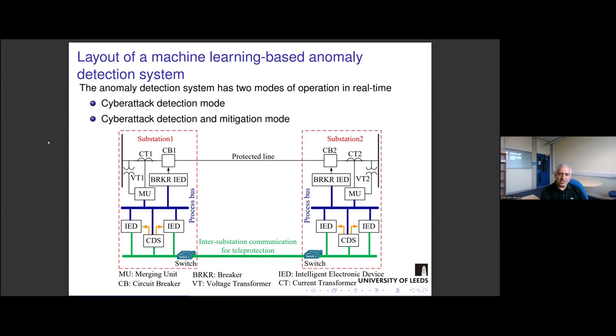We consider two modes of operation. This CDS, or cyber attack detection system, at the bottom of the figure is the one that we have developed. It has two modes of operation: cyber attack detection mode and cyber attack detection and mitigation mode. In the cyber attack detection mode, if it identifies an anomaly, it only generates an alarm to inform the operators of the substation that there is an anomaly in the measurements. And in the cyber attack detection and mitigation mode, after detecting the anomaly in the measurements, it immediately sends a command to the IEDs to block the malicious measurements, so the IED and the protective relays inside the IED don't trip the transmission line.